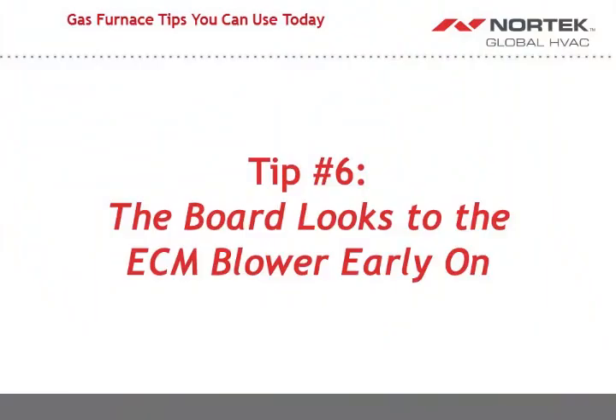Tip number 6, and it has to deal with ECM type motors, if you will. These are becoming more and more popular with every single passing season in the heating and air conditioning industry. The day is fast approaching where you'll be hard-pressed to even find a PSC motor out there any longer.